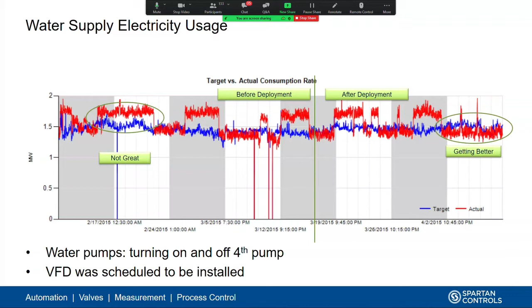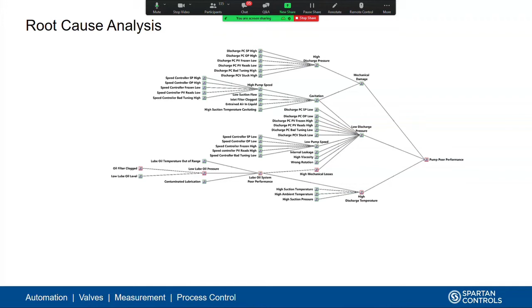So now what we're seeing is the next step in the evolution of EMIS, which is the incorporation of different analytic techniques. In this case, root cause analysis. What you'll see in the root cause analysis tree here is an example of a model that we've built. If I go back a slide, you'll see that at the very far right hand side, we have our actual symptom, right? In this case, the pump is showing poor performance. If we go back one layer, that poor pump performance can be caused by mechanical damage, low discharge pressure, or high discharge temperature. So there are 3 separate conditions that can be causing that poor pump performance.